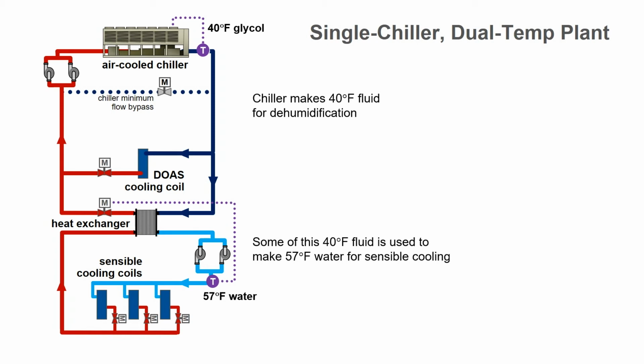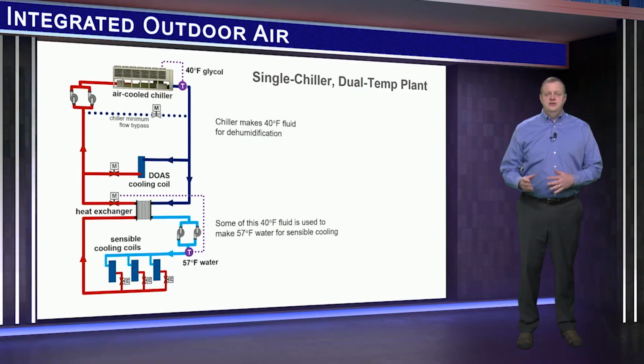The benefit of this configuration is its simplicity. The control valve for the heat exchanger is selected and controlled just like the valve on the dedicated outdoor air unit. And the delta T selected for the chiller and outdoor air unit is independent of the delta T selected for the terminal units. Plus, if glycol is needed for freeze protection, the heat exchanger isolates the glycol to only the water chiller and dedicated outdoor air unit. Pure water is used on the indoor side of the heat exchanger, so the terminal units are not affected by the glycol.